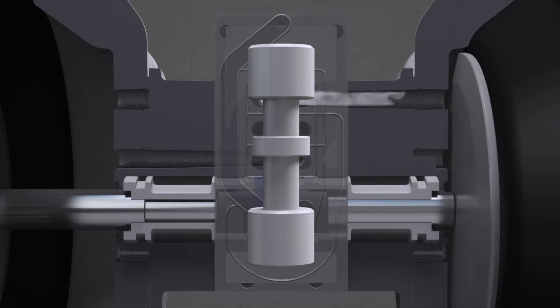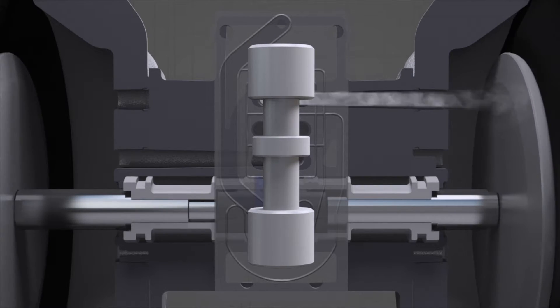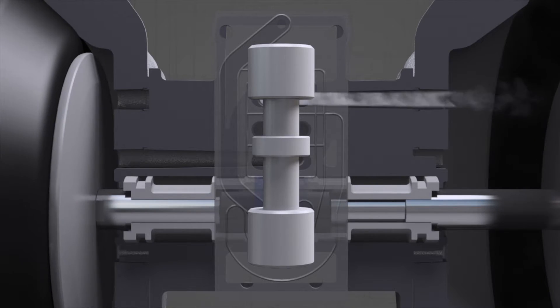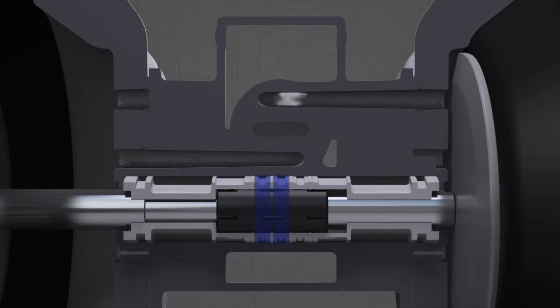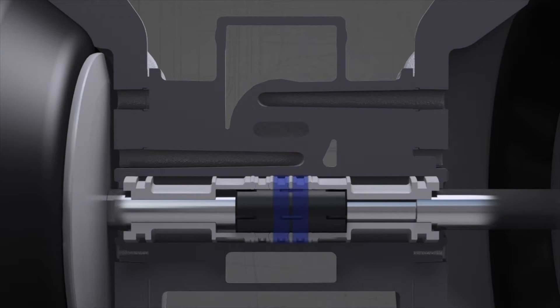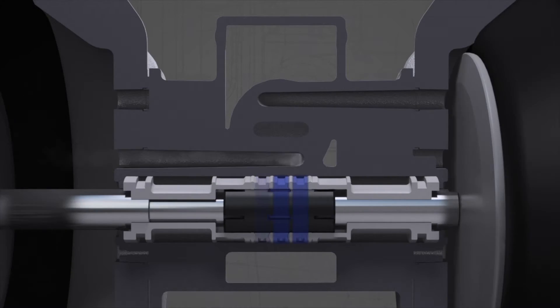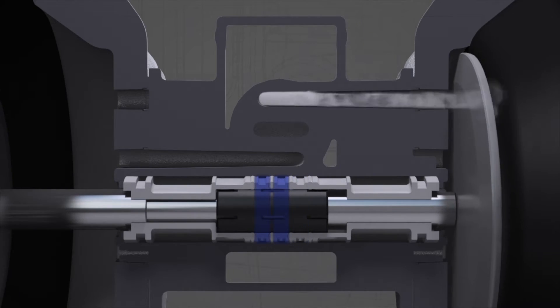This causes the right diaphragm to pressurize and the pilot valve to begin moving right. Throughout the cycle, one side pressurizes as the other exhausts. This process constantly alternates between the pilot and main air valve to create a continuous cycle.